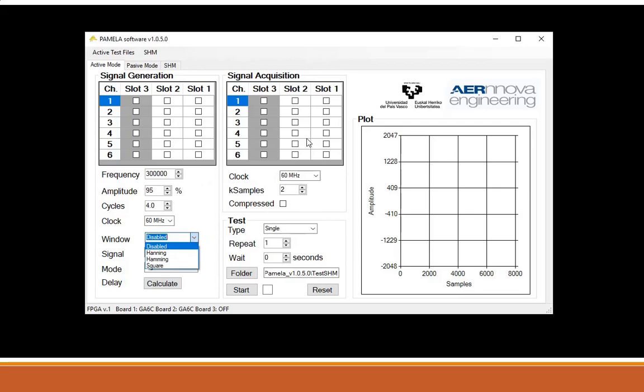On the acquisition configuration part, the selection of the sensors that will be read is carried out. The full waveform can be retrieved or only the characteristic points in the compressed mode. Finally, the type of test should be selected. It ranges from single, usual pitch and catch, round robin, where every generating sensor drives the unit under test sequentially and the acquiring sensors capture the incoming signals. Beamforming aims at focusing the energy on a given direction on a given angle. Finally, multiple signal delay applies arbitrary delays to any generated signals.